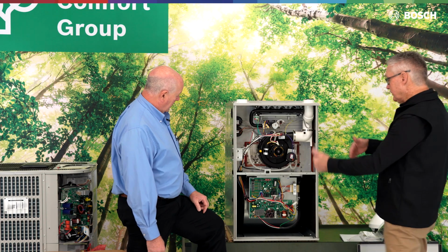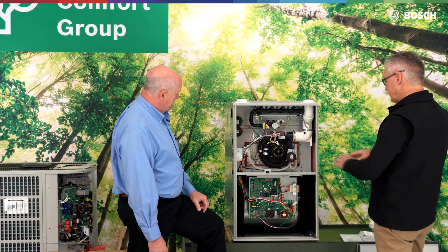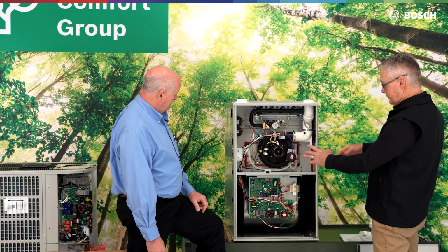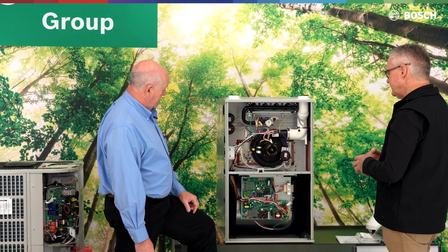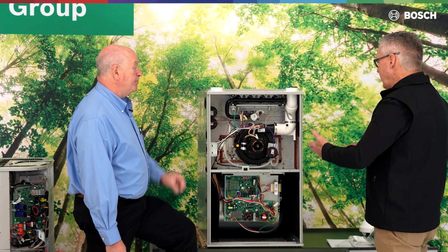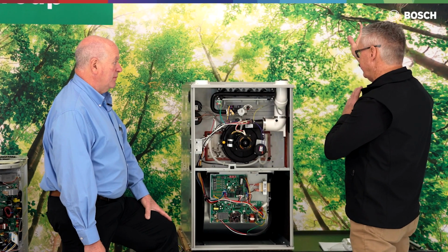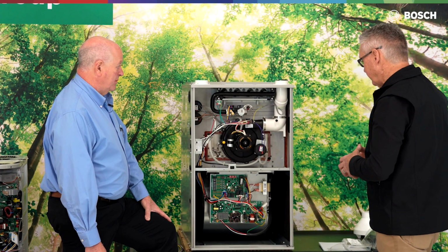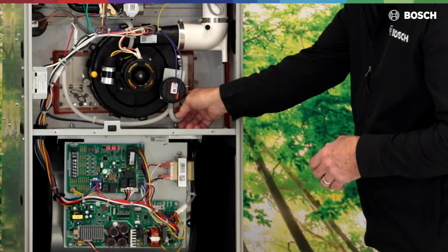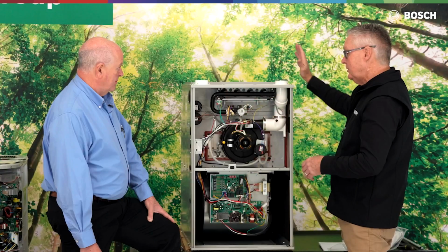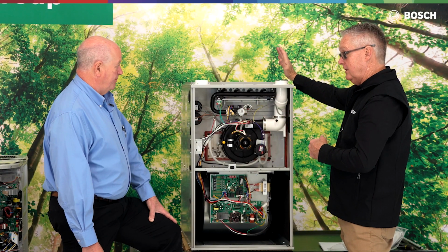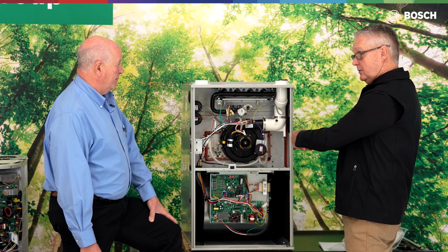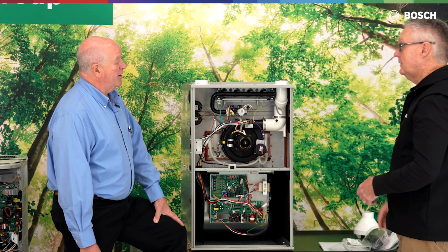So in this particular furnace, if my filter gets dirty and my blower wheel gets dirty, and I lose the ability to blow the air through the ductwork like I needed to, that secondary heat exchanger is first in line to the coil that we're fixing to put on here. So that would get dirty also, right? Oh yes, and they're hard to clean.